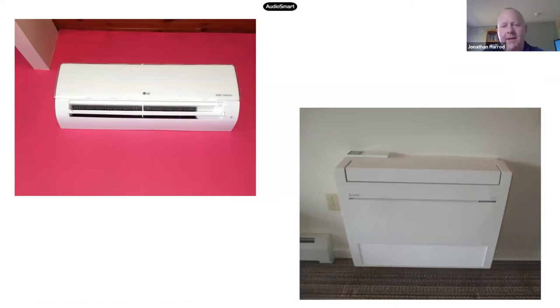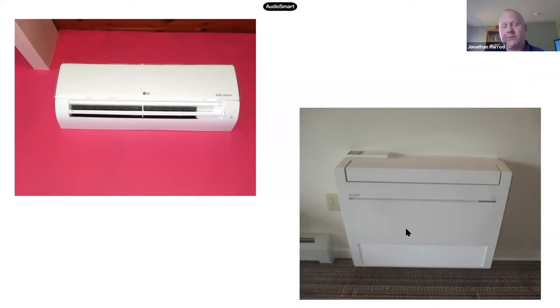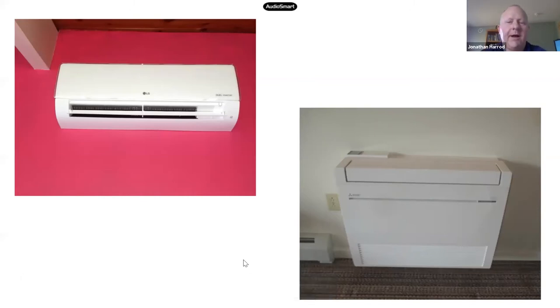Because we're primarily a heating climate rather than a cooling climate, in some ways it's actually even more ideal to have our heat emitters low in the room. And these are a solution for that. These, what we call floor units, are actually attached to the wall just a few inches above the floor. They're pulling in the coolest air close to the floor and heating it, blowing it out. They work fine for cooling in our area. The main reason I think we don't install more of these is that people tend to have more free wall space higher up in the room, and most of the space low in the room is covered with furniture.